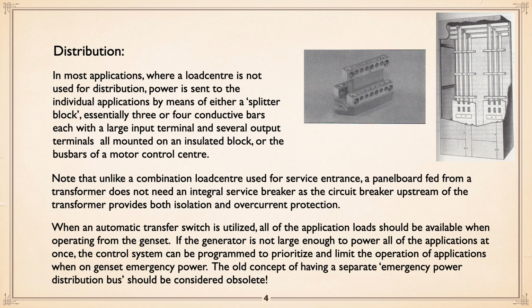Distribution of that power, once you get past that, in a control panel or whatever, you will have a splitter block, which you can see in the picture on the left, which basically has an input terminal and then a whole bunch of little output terminals. And in a motor control center, as we looked at before, this is sort of a cutaway, you have the horizontal buses bringing in, and the vertical buses that split off that basically are the distribution to the various devices.